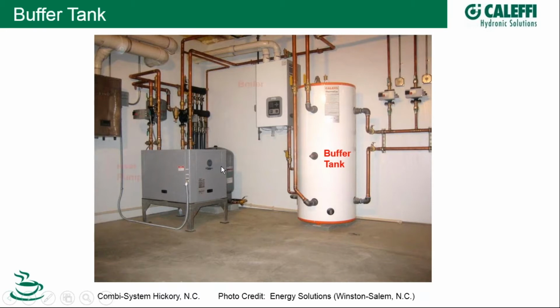Over on the primary side, we have 2 sources of generating heat. We have a heat pump. It's a ground coupled heat pump we can see, because against the wall here, we can see the polyethylene tubing going down into the ground. Let's see, which way would it be going down? This would be the return. Yeah, going down into the ground and the return back this way. Okay, so it's actually a heat cool system in this building.